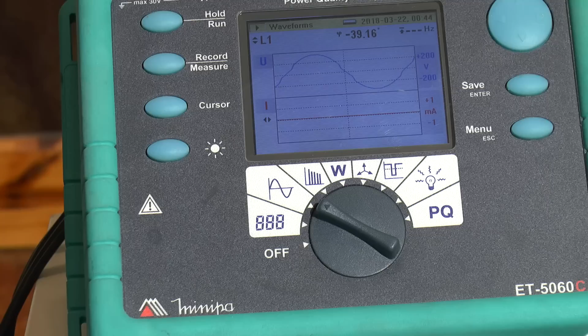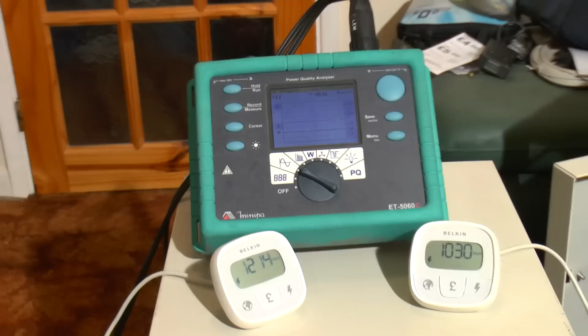And we're back. Now let's see what happens if we load it to the max, where instead of having the 100 watt lamp, we'll take it to the limit with a 1000 watt lamp. Now of course there's going to be inrush with this as well, so it might not like it, it might just shut down. It's running it, but not very efficiently. You see we've now got 1200 watts in, 1000 watts out, so it's not the most efficient of UPSs. The waveform is absolutely rock solid, it doesn't seem to make a difference. In fact, it gets slightly quieter when it's running the lamp.